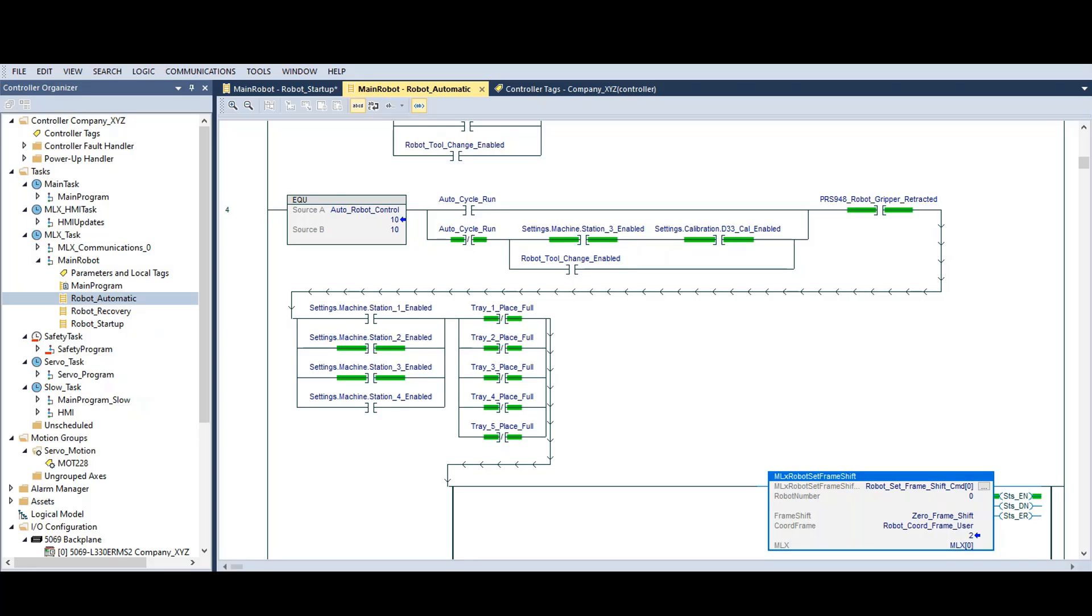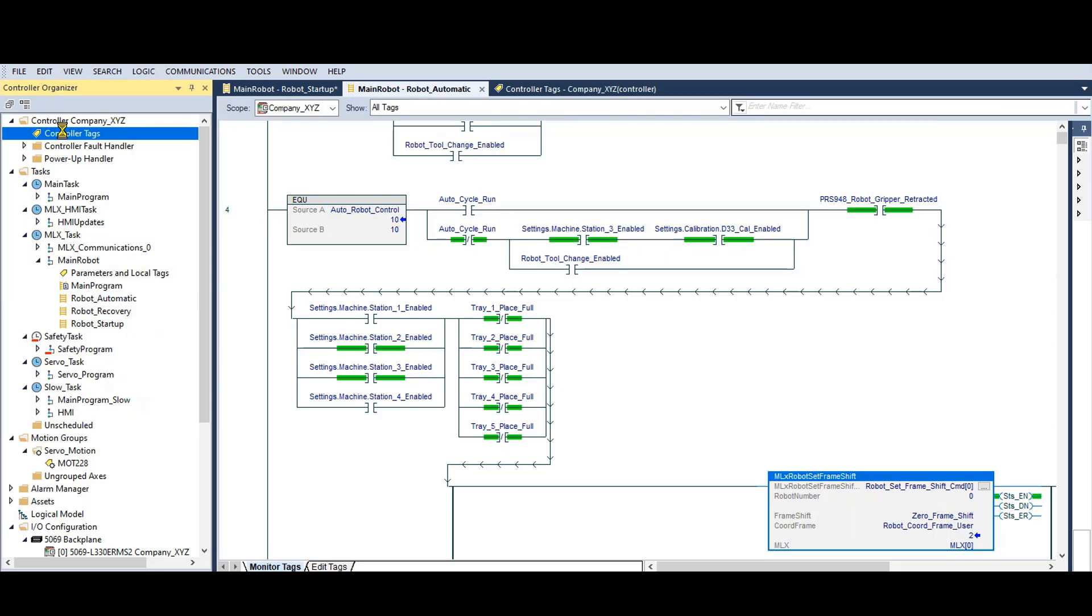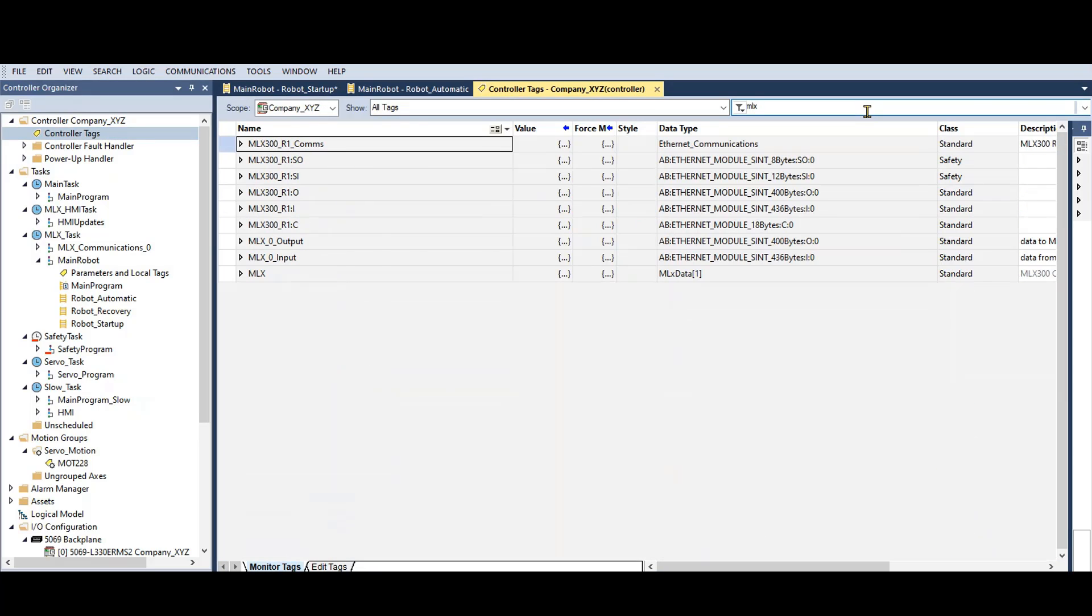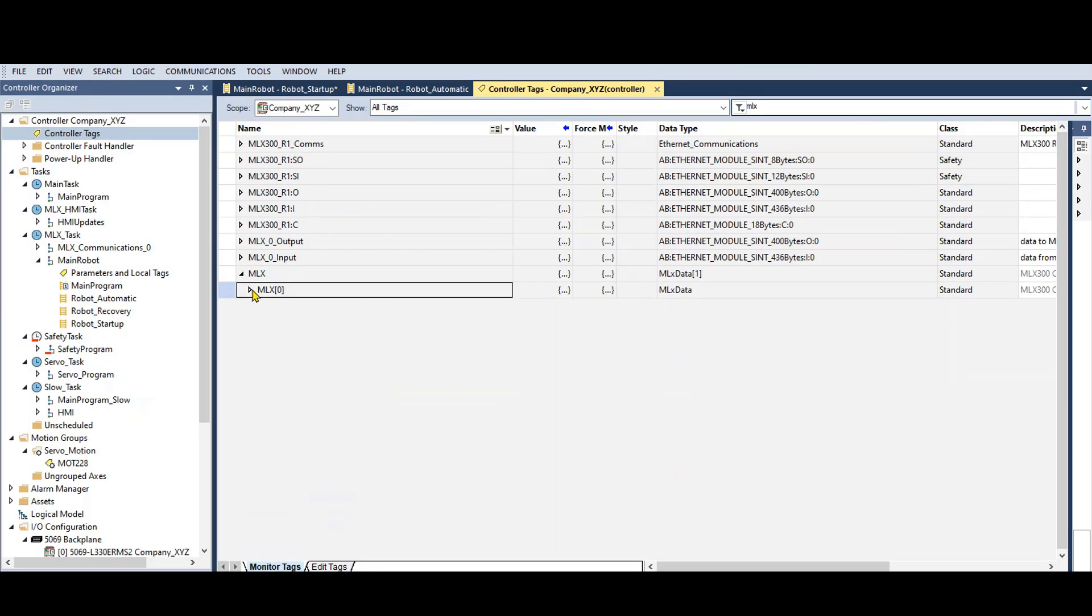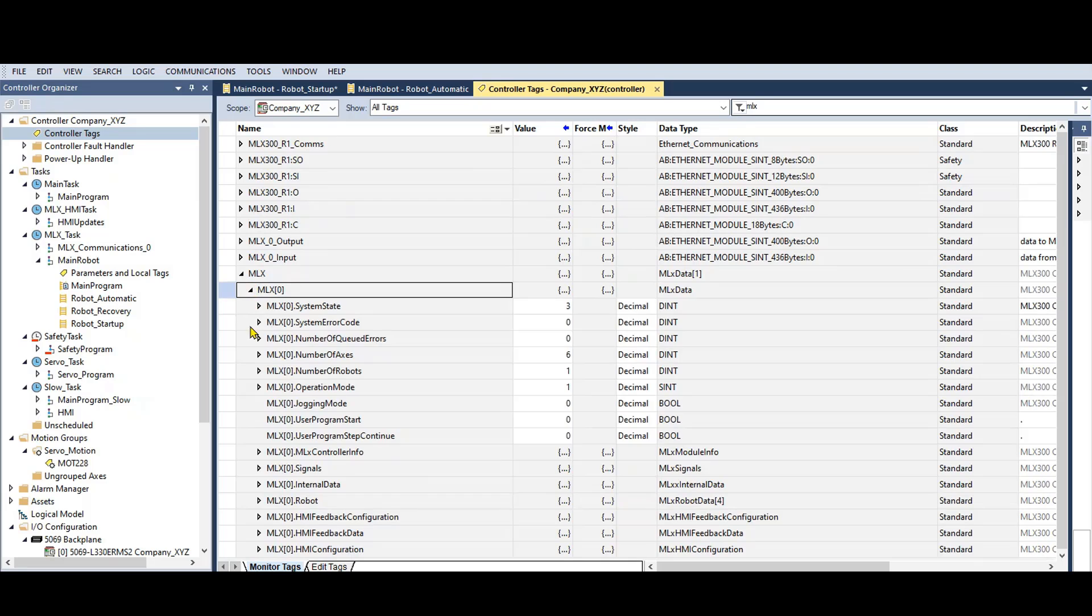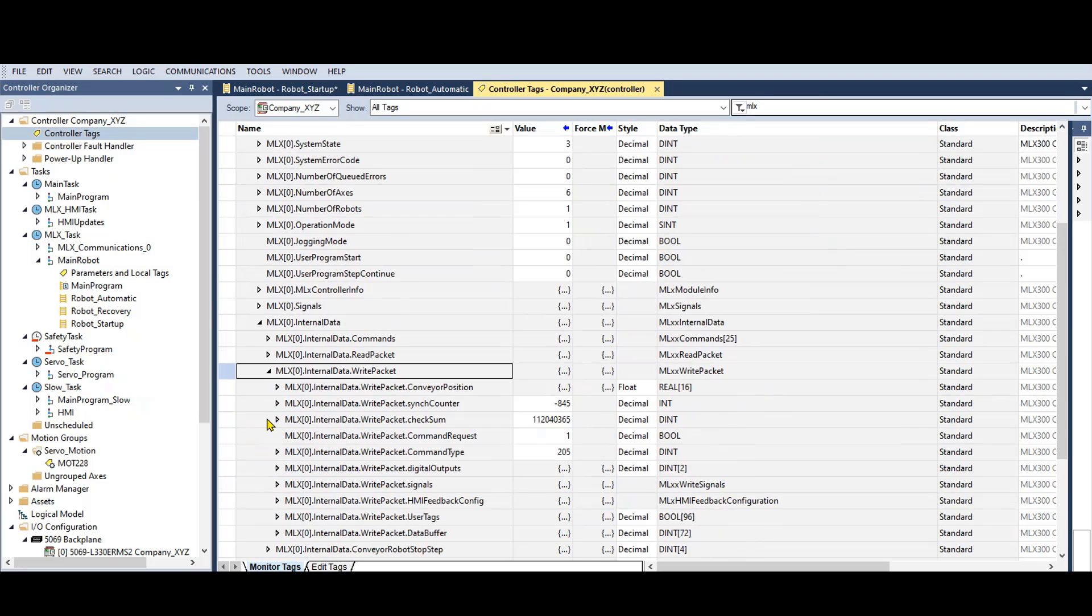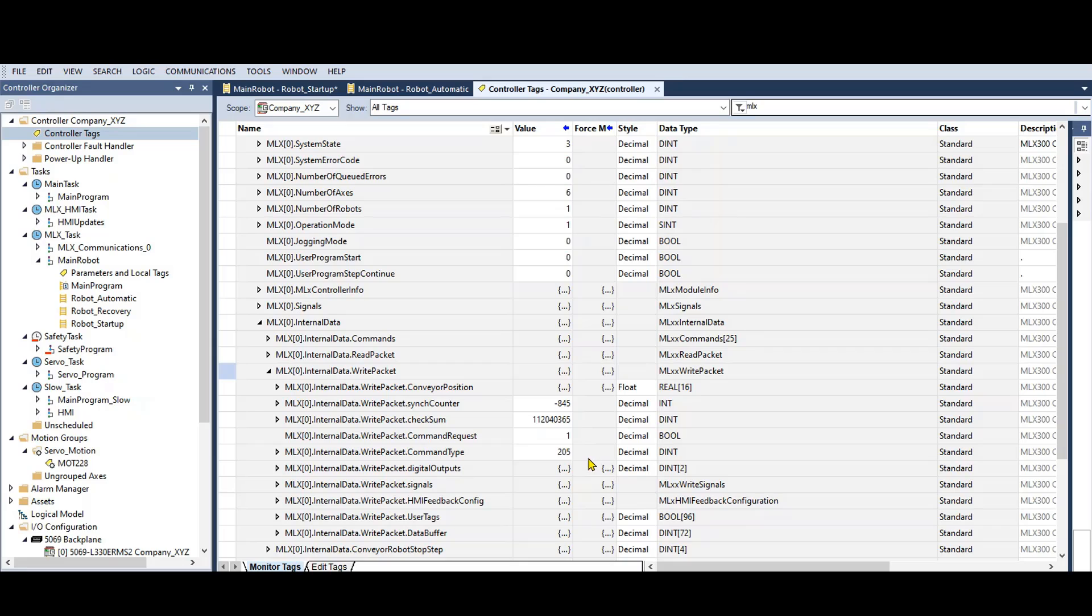I'm going to show you the process of the second option. You can look at the MLX tag array to determine the last command that was executed. Go to the internal data, write packet, and you will see there is a command that was requested but wasn't finished. You can tell it wasn't finished because the request bit is still on.